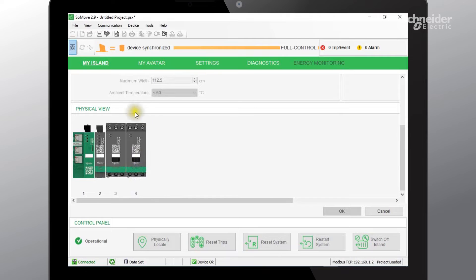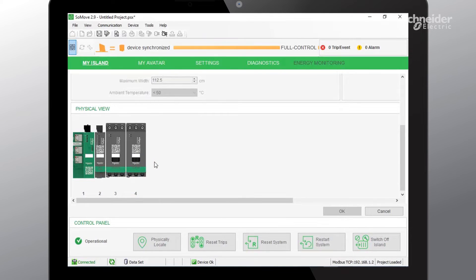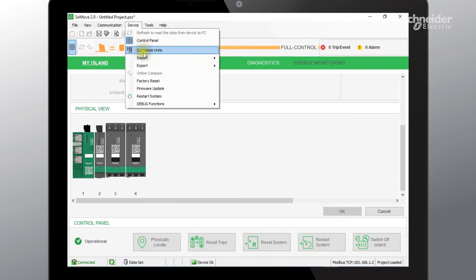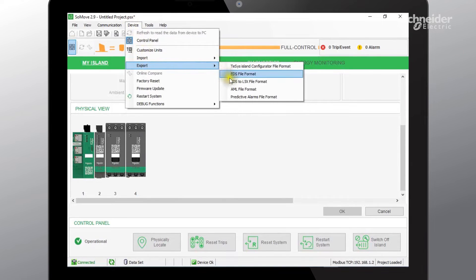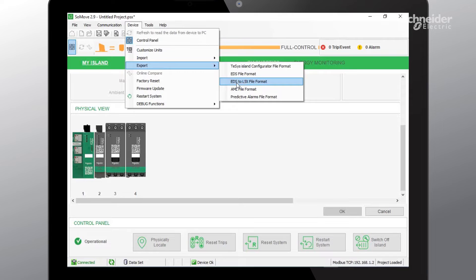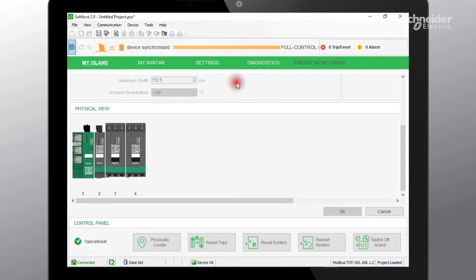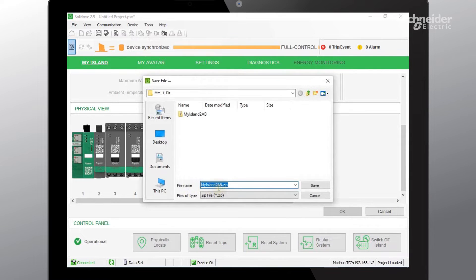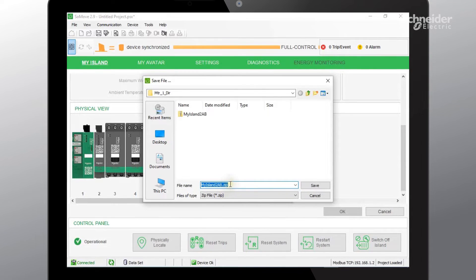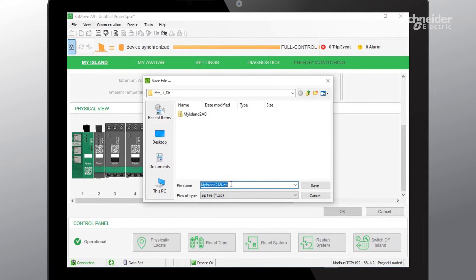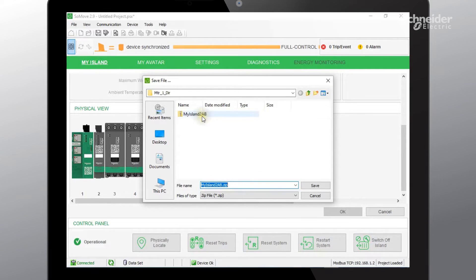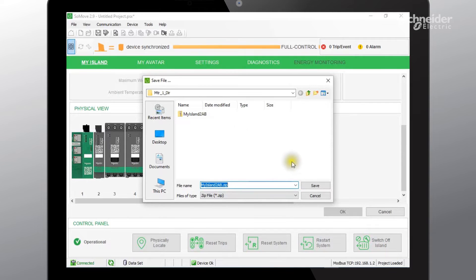Now that we've pre-configured our TeSys Island, we will need to export this out to the Allen Bradley Studio 5000 software. To do that we'll need to go to device, export EDS to L5X file format. We'll select that. In this file name that is being created, it is going to be a zip file, a compressed file that has three individual files located in that compressed file. I've already gone ahead and saved it and decompressed that file. So I'll go ahead and hit cancel.